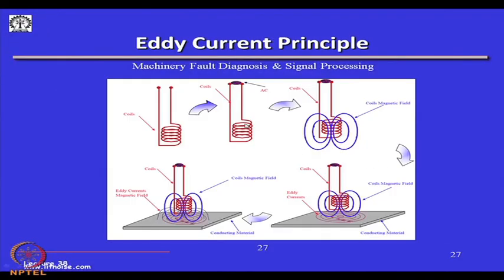The principle behind eddy current testing: if a coil is supplied with a high-frequency AC signal, there will be a magnetic field associated with this coil. If this coil is brought near a conducting material, because of its magnetic field, a series of circular eddy currents will be formed. These eddy currents will also produce a magnetic field. If there is a defect or change in thickness in the conducting material, the magnetic field produced by these eddy currents will be different.